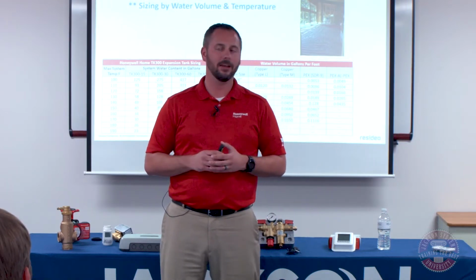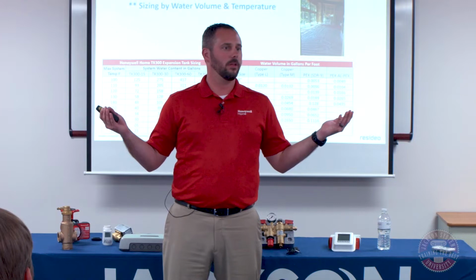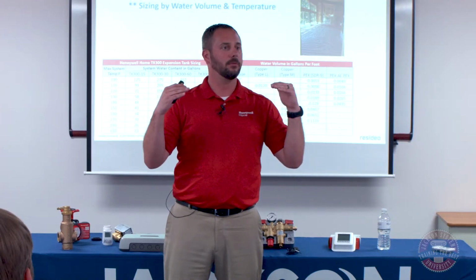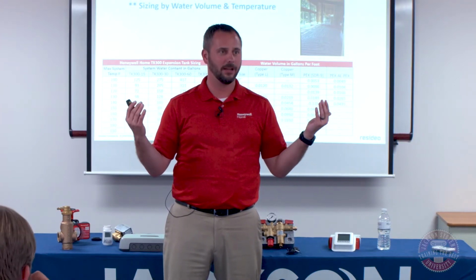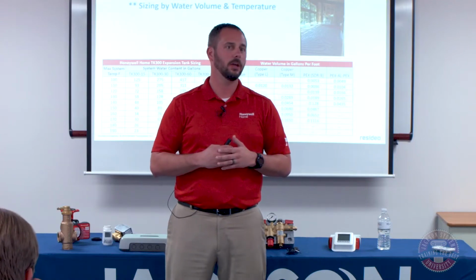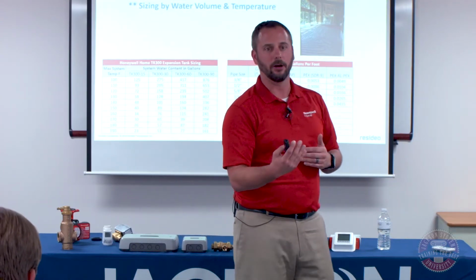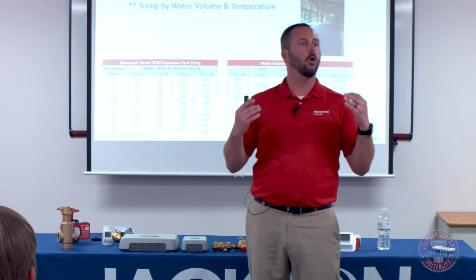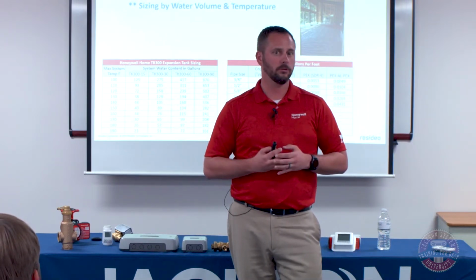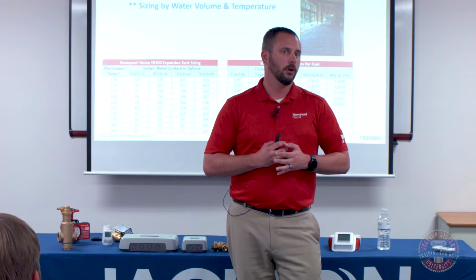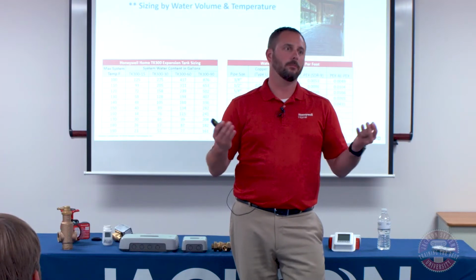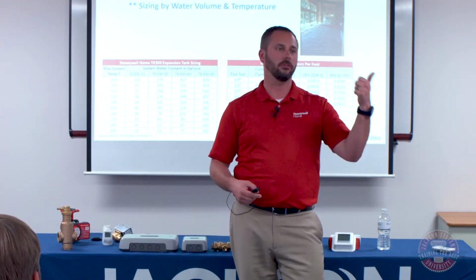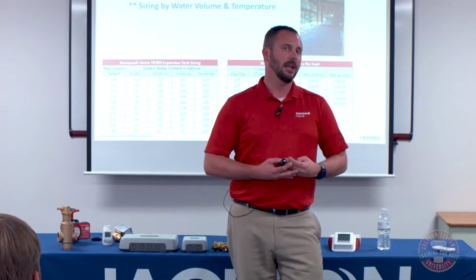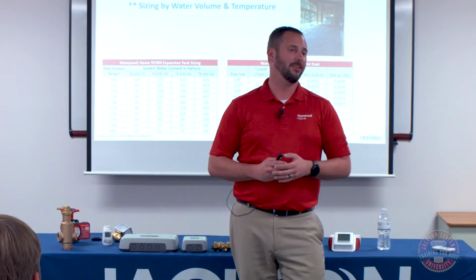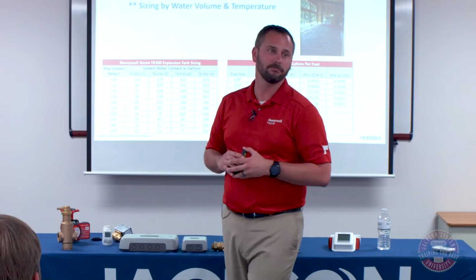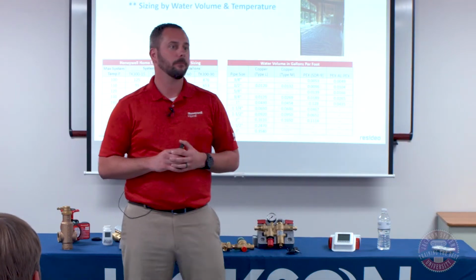And the reason I say that is it's nothing more than a diaphragmed air tank. So your expansion, regardless of which way it's oriented, is going to be pushing against that air bladder. The reason that you'll see it always mounted down in the installation manuals is because of that Schrader valve. If you ever have to bleed water off, you always want to bleed water towards the floor instead of towards the ceiling, against the wall, etc. We always show it down, but in practicality, it really doesn't matter. But great question.